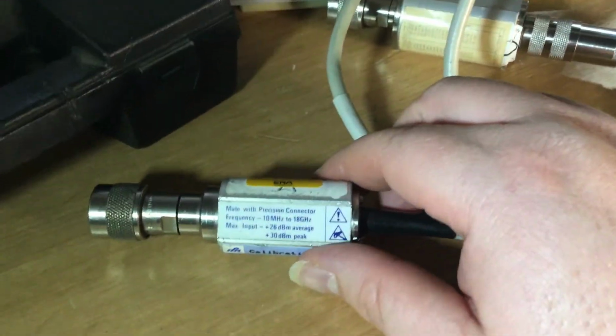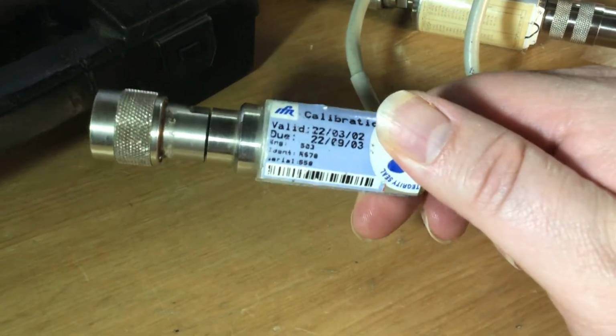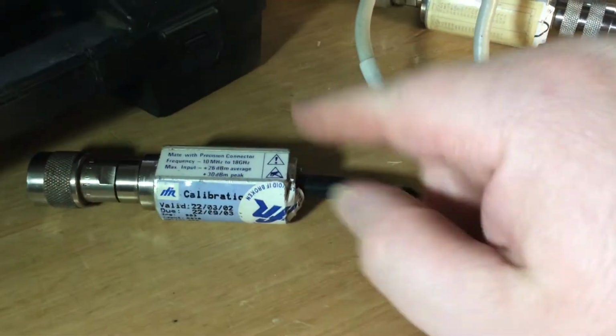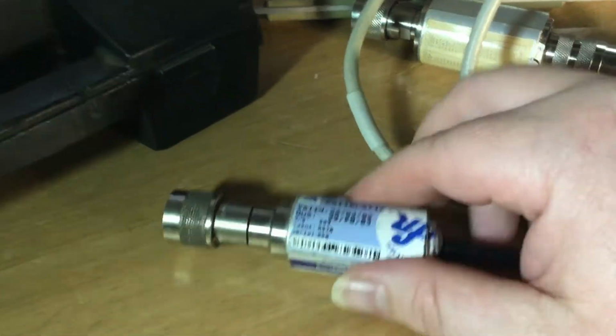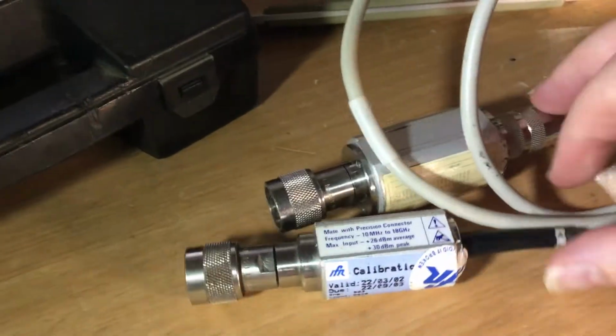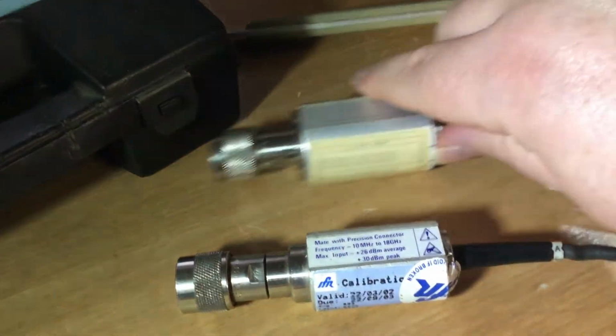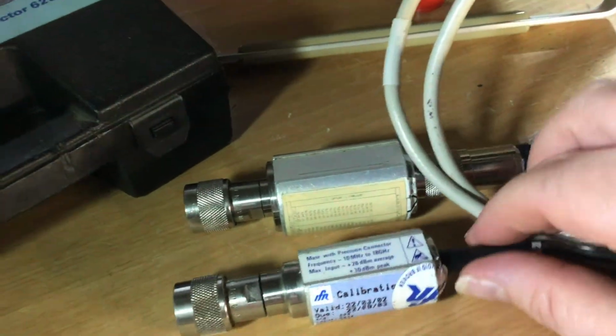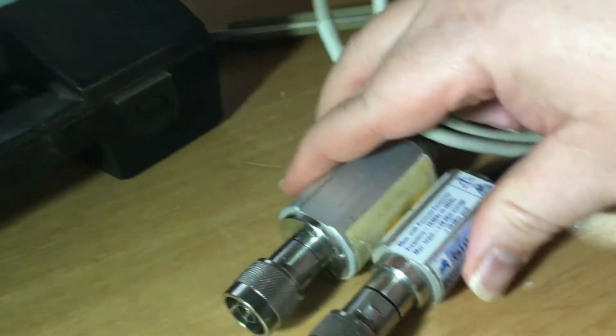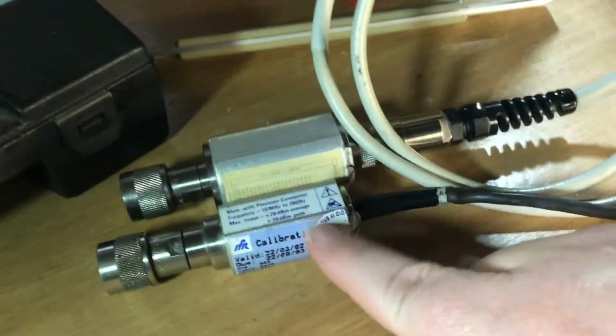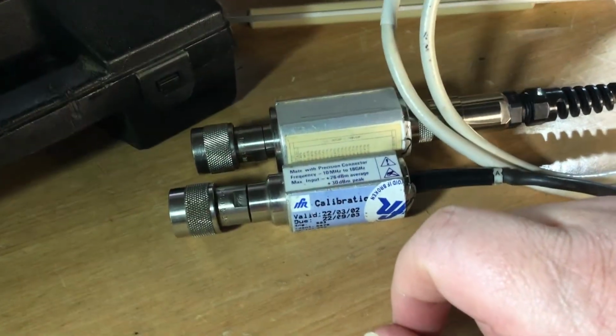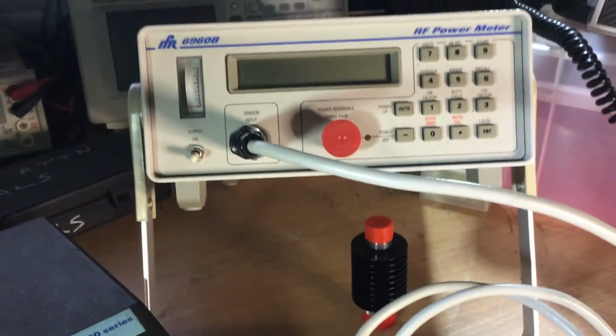So this is what we were referring to earlier as being the SCALAR sensor, where the wire connects directly in. They look very similar to the RF power sensors, obviously side by side. There's not much real difference between them in size, just a little bit maybe, but the SCALAR sensor can't be used as an RF power sensor with that meter.